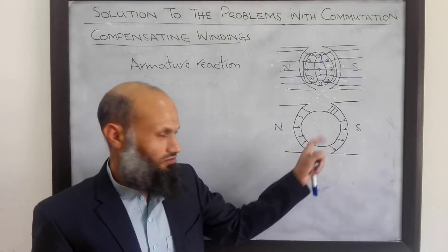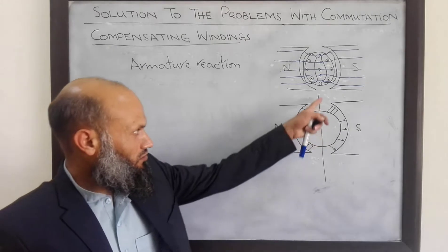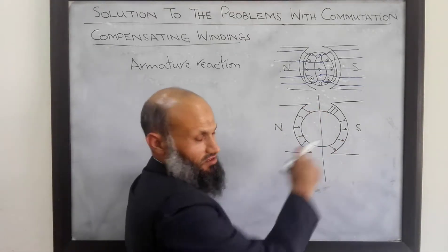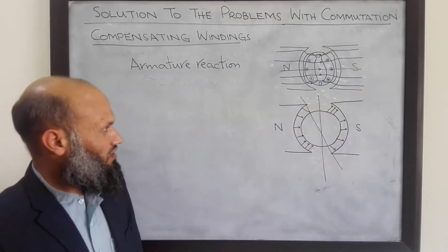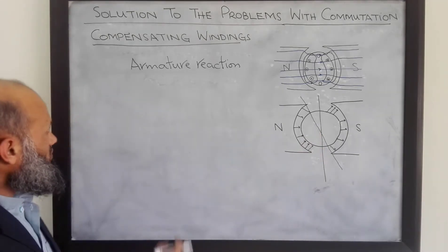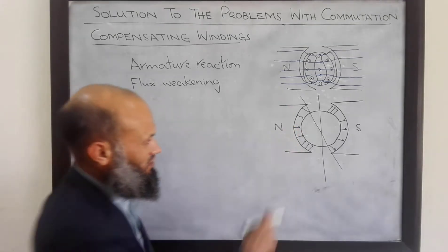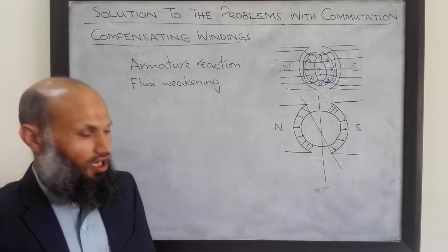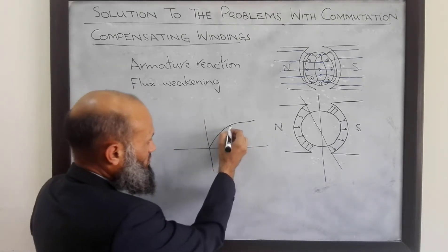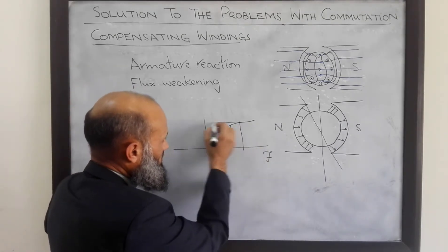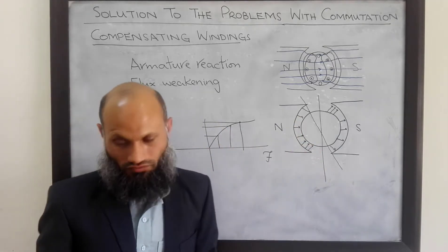There are two consequences of armature reaction. The first is a shift in the neutral plane — ideally the neutral plane should be at a fixed location, but due to distortion in the magnetic field, this neutral plane is shifted to a new location. The second problem is flux weakening: at one end of the pole MMF is increased, at the other end MMF is decreased, and net MMF is the same. However, due to saturation in the magnetization curve, the increase in flux is not equal to the decrease in flux, so net flux in the machine is decreased — this is flux weakening.